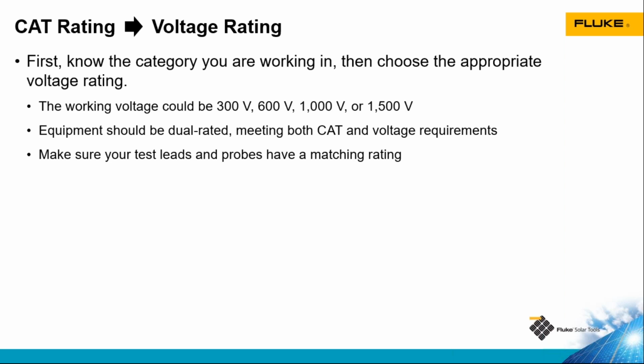We may be testing a single module, which might be 30, 40 or 50 volts, up to 600 volts on residential, 1,000 volts on commercial, and up to 1,500 volts on utility scale projects. We also see an array of AC voltages from 240 volts in residential settings up to 600 volts in utility scale projects, and now our utility scale inverters are even moving to 800 volts.